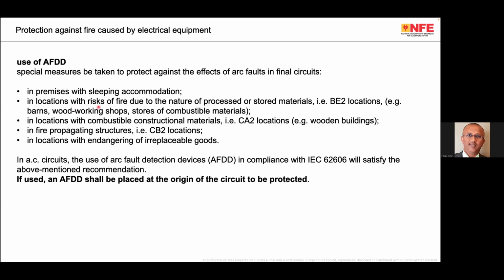It is recommended in locations with risk of fire due to the nature of processed or stored material, for example BE2 locations; in locations with combustible construction material, CA2 locations; in fire propagating structures, CB2 locations; and in locations endangering irreplaceable goods such as museums or heritage buildings. If used, the AFDD shall be placed at the origin of the circuit to be protected. This device, AFDD, has been recommended in both NEC as well as IEC 60364.